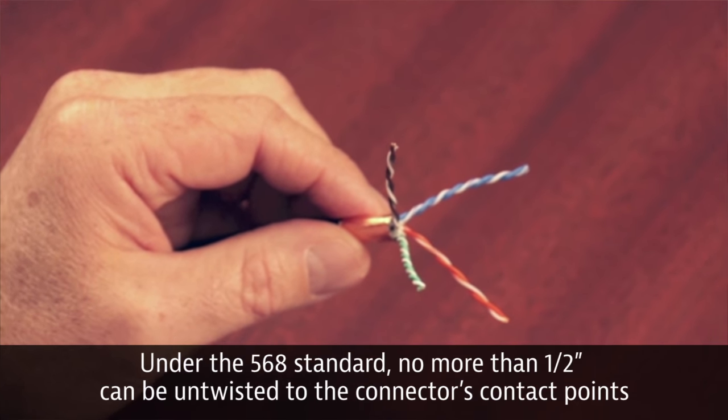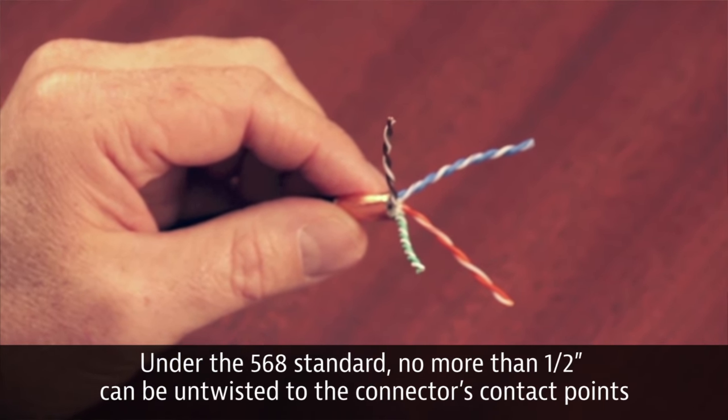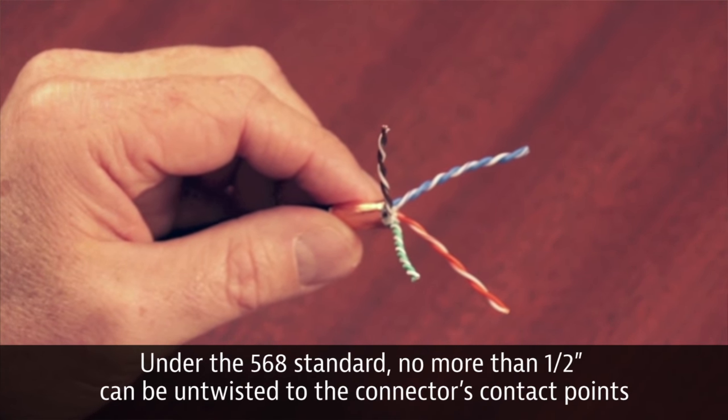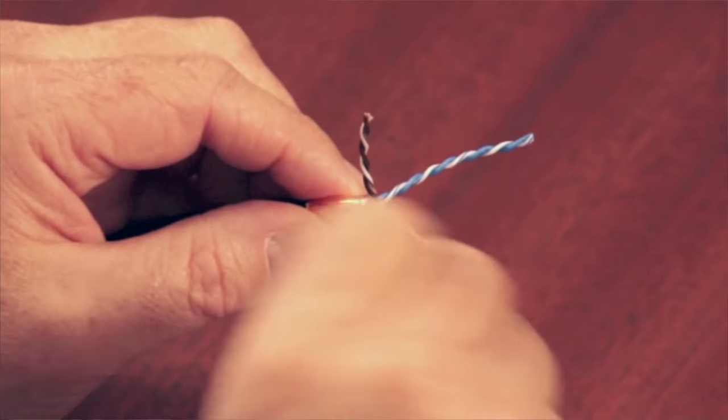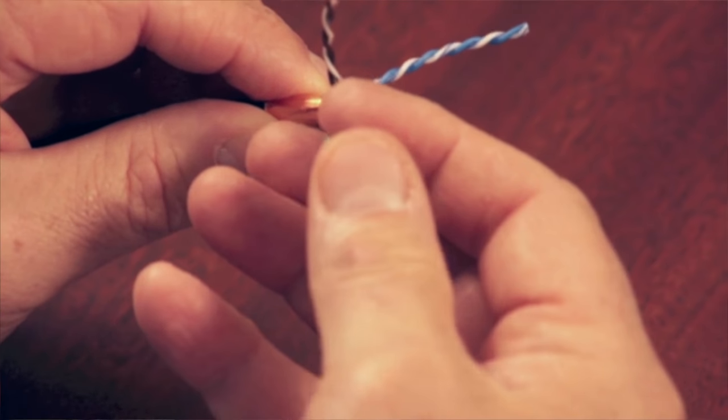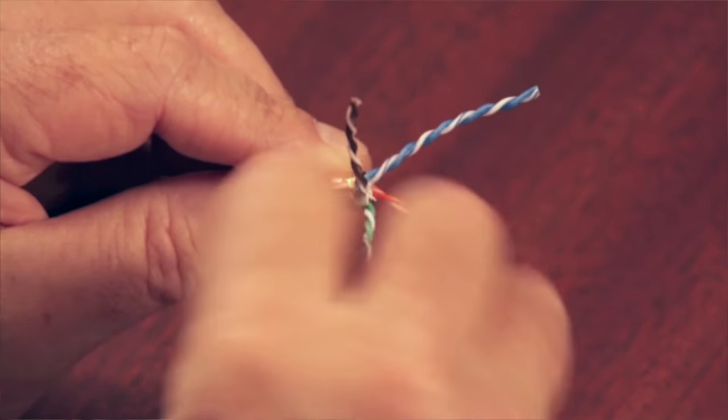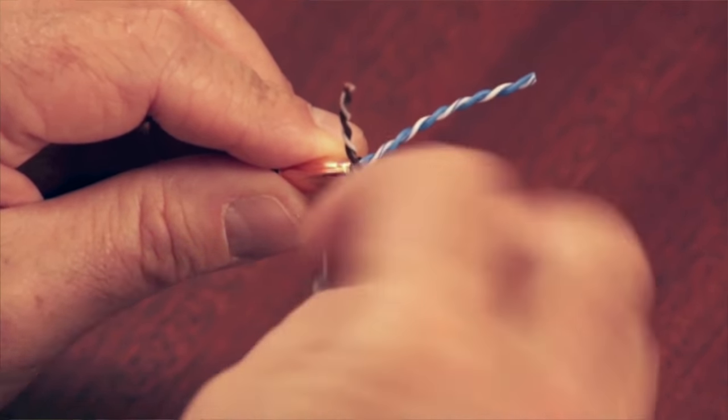Next we're going to untwist our pairs. Under the 568 standard, no more than one half of an inch can be untwisted to the connector's contact points. Make sure you untwist these, and keep your tip and ring conductors together. The white is the tip conductor and the colored is your ring.